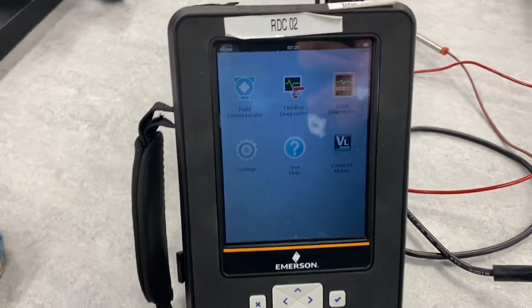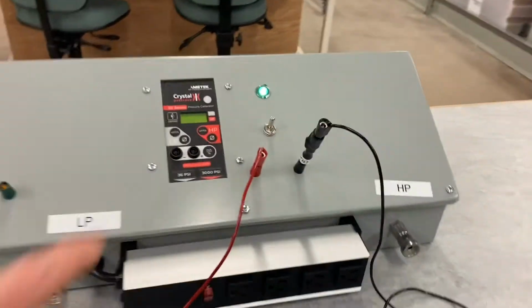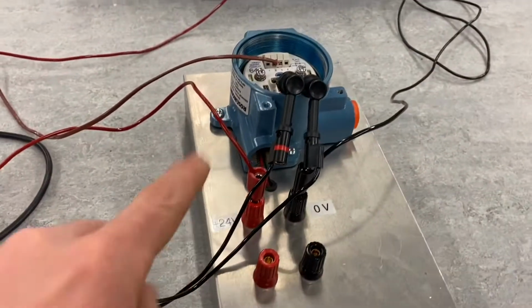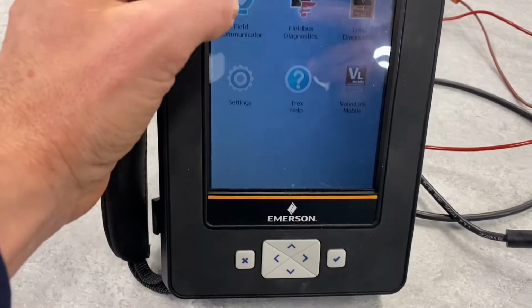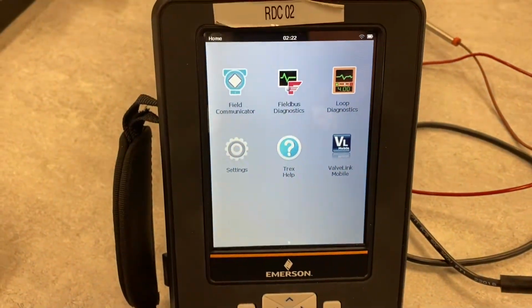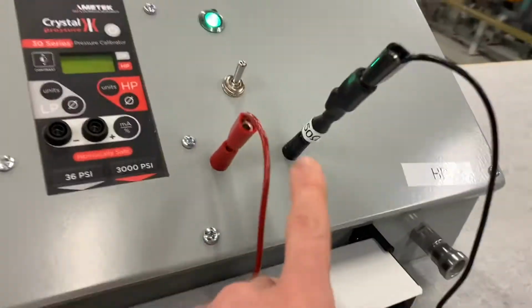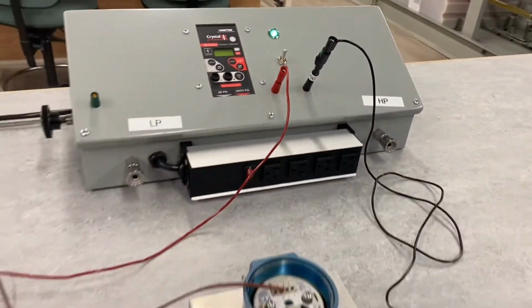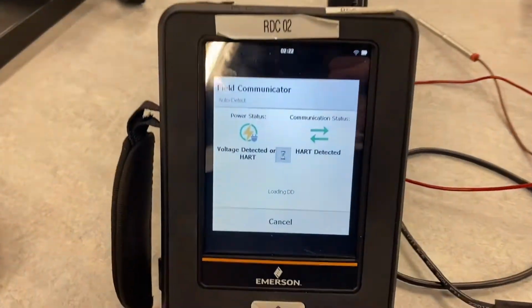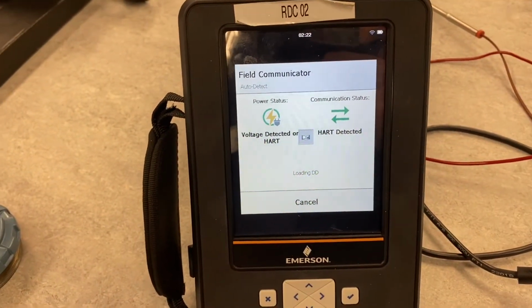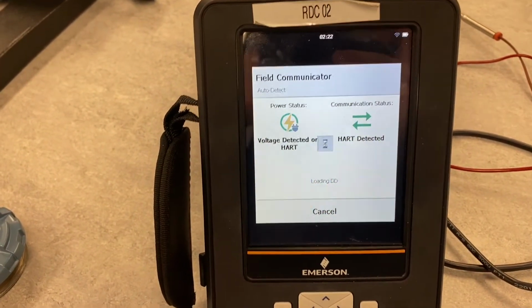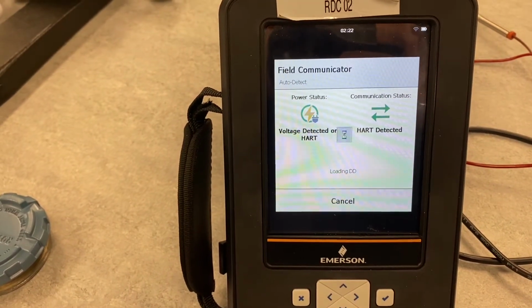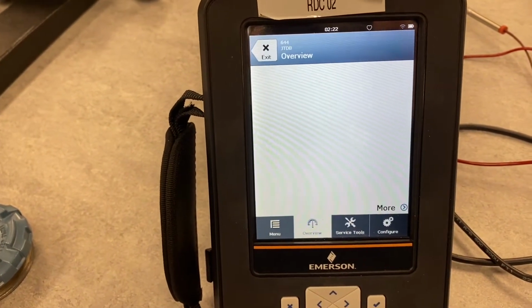We've got it powered on here. There's just a power button over on the side. I've got power, green lights illuminated here. We've got 24 volts going to our transmitter. So if we just click on the field communicator right here, it should open up and try to talk to our device. I want to stress the importance of this 250 ohm resistor here. It's a requirement for HART protocol to be in the loop so it can talk. If it's not there, you won't be able to talk to the device. So it's just connecting to the device right now.